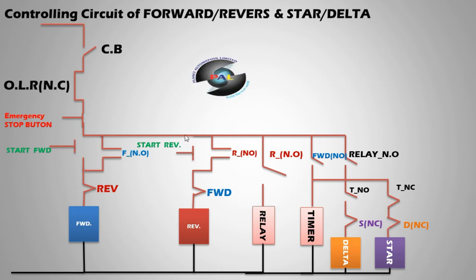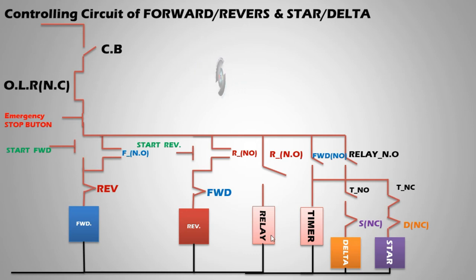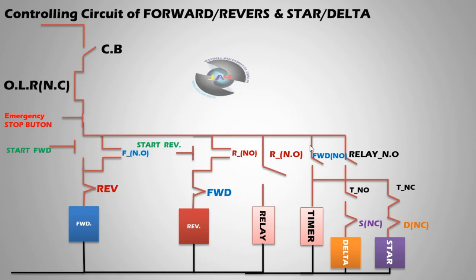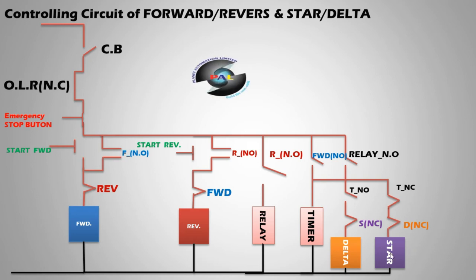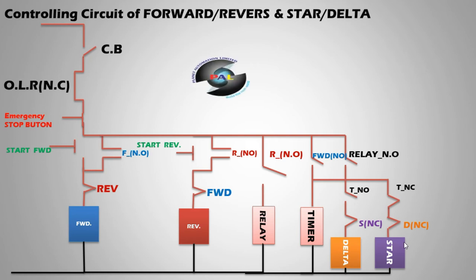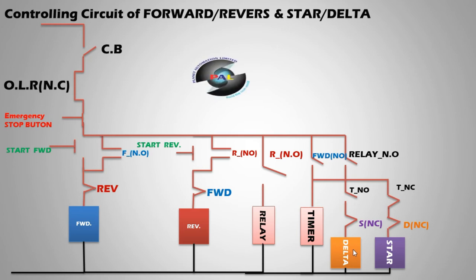For forward operation: when the forward button is pressed, the relay turns ON. When the relay is ON, you connect to forward, and the timer is connected to maintain star and delta. Initially the motor starts in star, and then after 20 or 15 seconds, the star turns OFF and delta runs.